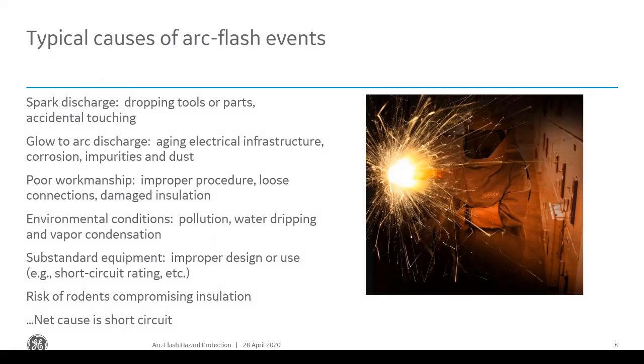So there are many causes for arc flashes, but most of the typical ones are listed here. Accidental dropping of tools or broken parts can cause multiple short circuits and initiate arcs. Aging components, corrosion, and impurities result in insulation deterioration and, in time, the release of arc flash through that deterioration. Poor quality work, such as loose connections and damaged insulation, can severely compromise the connection quality and cause arc flash incidents.